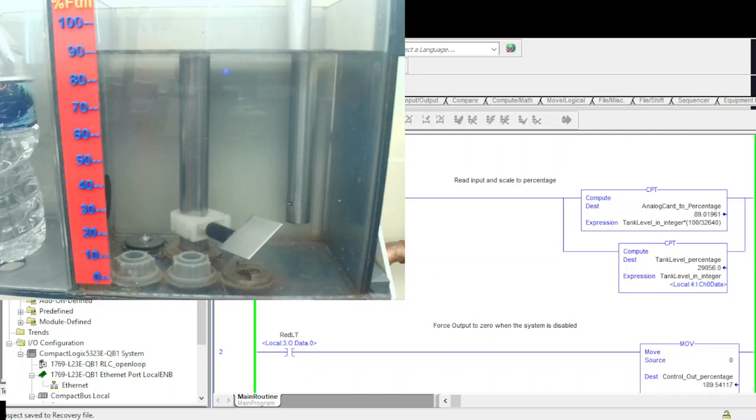Okay, so my slope for the level sensor is, I want it to be a percentage, so it's 90% minus 20% divided by the integer value at 90%, okay, which is 29,100 minus the integer value of 20, which was 7,700. All right, so that's my slope.